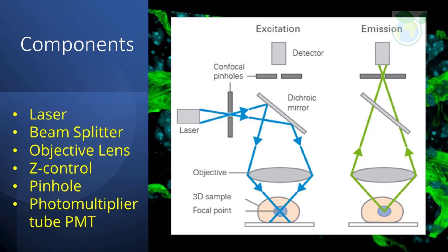Another component is the objective lens. These are the heart of the microscope and mainly determine the optical image formation and the resolution of the system. Besides that, we have the Z-control, which allows you to focus on any focal plane within your sample, and the motorized Z-stepper allows movement in the axial direction in small step sizes smaller than 10 nanometers with high precision.